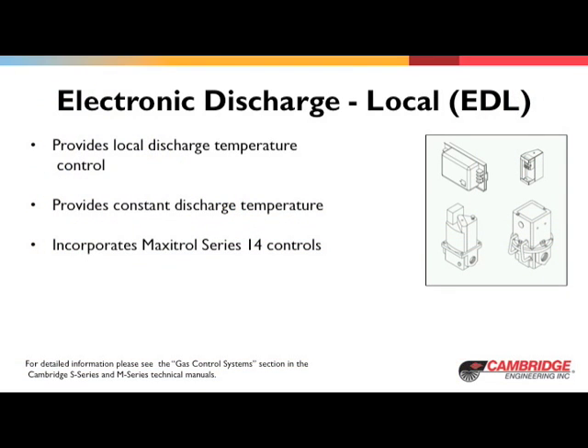Electronic Discharge Local, or EDL. The EDL control system is only used on S-series heaters. The EDL provides local discharge temperature control. The discharge is determined by a potentiometer on the front of the amplifier in the electrical enclosure of the heater. EDL provides constant discharge temperature, which is typically 160 degrees.